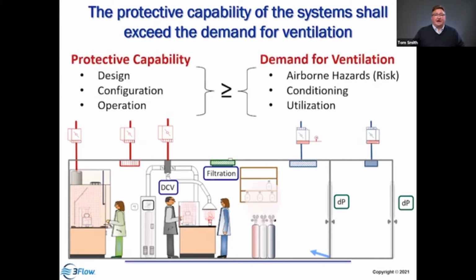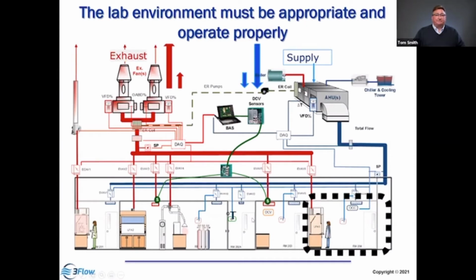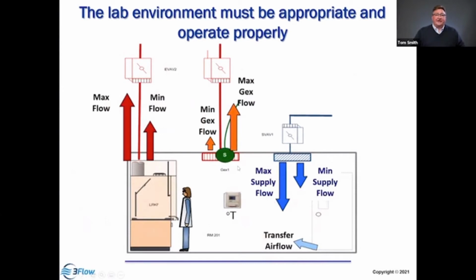Looking into the laboratory again, the protective capability should always exceed the demand for ventilation. And if we do that properly, we're going to mitigate the risk. We want to start with the laboratory and look at what's in that laboratory. What are the hoods? What's the general exhaust? What kind of air supply? How are they working together to provide a safe environment? And what are the minimum and maximum flows? Someone has to program this. And when we test it, somebody has to tell us, what is it we're doing? What are we looking for in terms of safety?